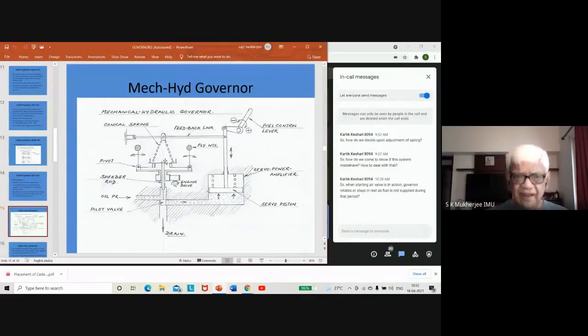Now here you have the spring which is pushing down the speeder rod, and the flyweights again through bell crank levers are pushing that collar which is holding the speeder rod upwards. So there are counterbalancing forces between the spring and the centrifugal force, and both of them are ultimately holding the speeder rod. This speeder rod, instead of directly controlling the fuel rack, because it does not have so much power, so much force, and to move the fuel racks you require a lot of power. And believe me, you or me, we cannot do it by ourselves. Even if we use our maximum strength, we cannot.